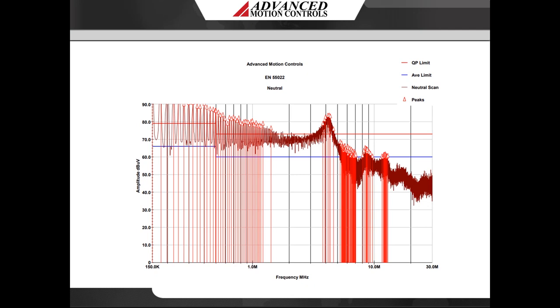Conducted emissions testing focuses on the emissions generated by the servo drive that are transmitted along the AC power line. With the use of test equipment — a spectrum analyzer and a line impedance stabilization network — the servo drive can be tested to measure the level of conducted emissions and verify they comply within the limits set for Class A devices. A typical frequency range for conducted emission standards is set between 150 kHz to 30 MHz. Without additional filtering, peak amplitudes are above the acceptable quasi-peak limit line and the device would not pass compliance testing. Peak detection retains the peak value of the emitted noise signal and indicates the worst case scenario, since peak values will always be greater than the quasi-peak values. Regulatory compliance testing requires quasi-peak amplitudes to be below the quasi-peak limit line for the product to pass.